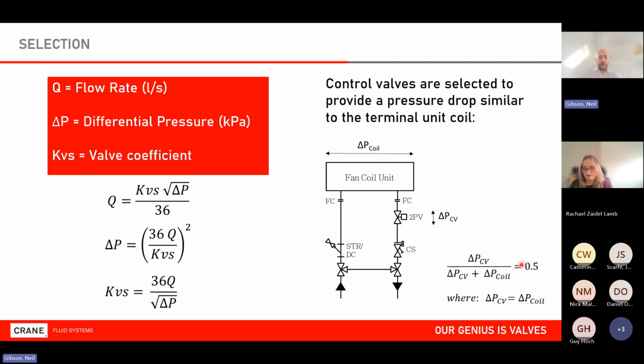The reason being valve authority: as the 2-port valve modulates, we actually get a response in the system. If we have a very poor valve authority, what we'll have is a modulating valve which does nothing until it shuts, which is not the most energy efficient solution. So we need a reasonable valve authority, in this example, 0.5 in the context of control valve and coil.